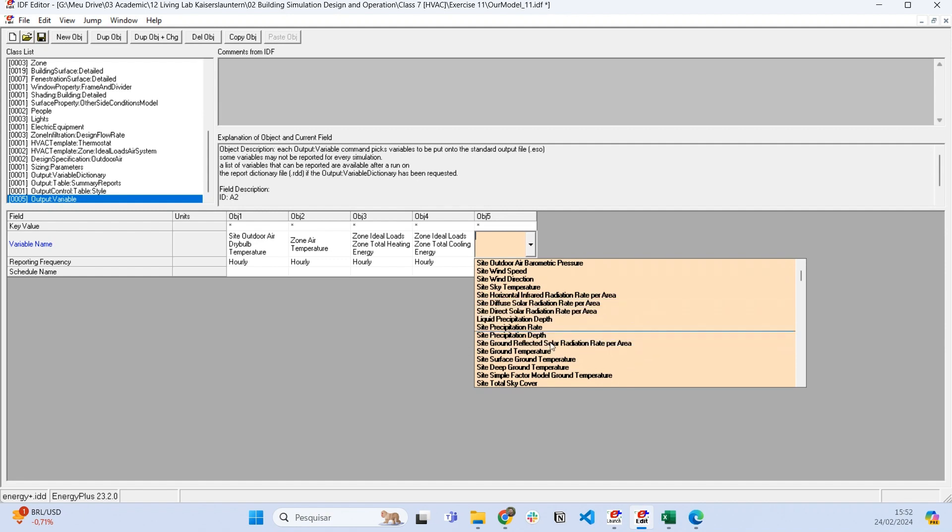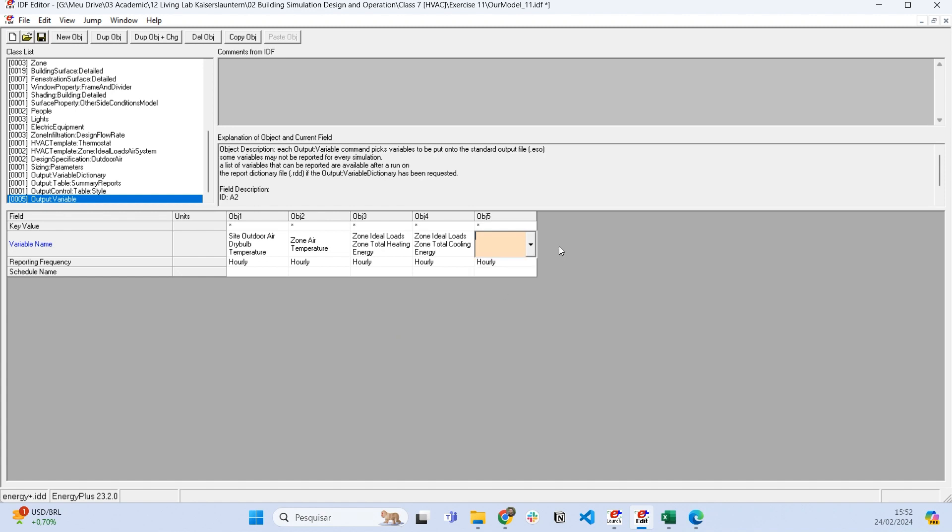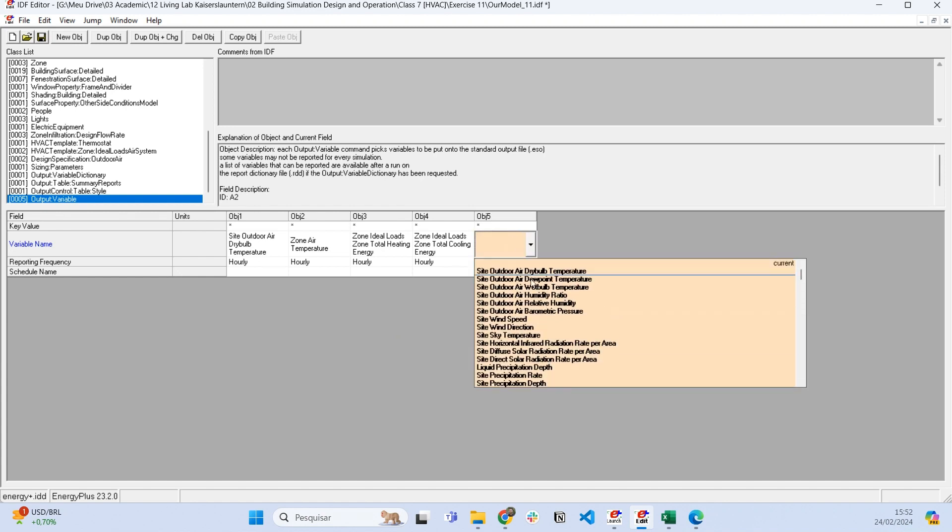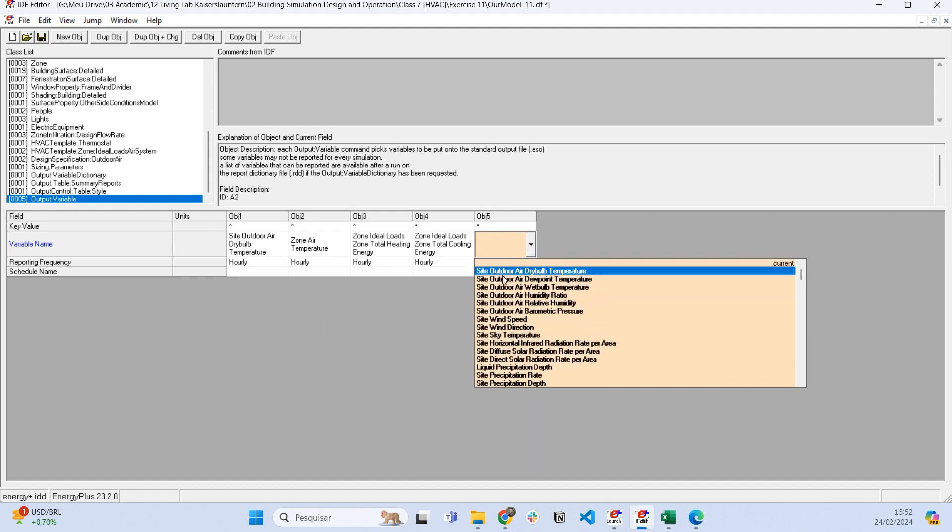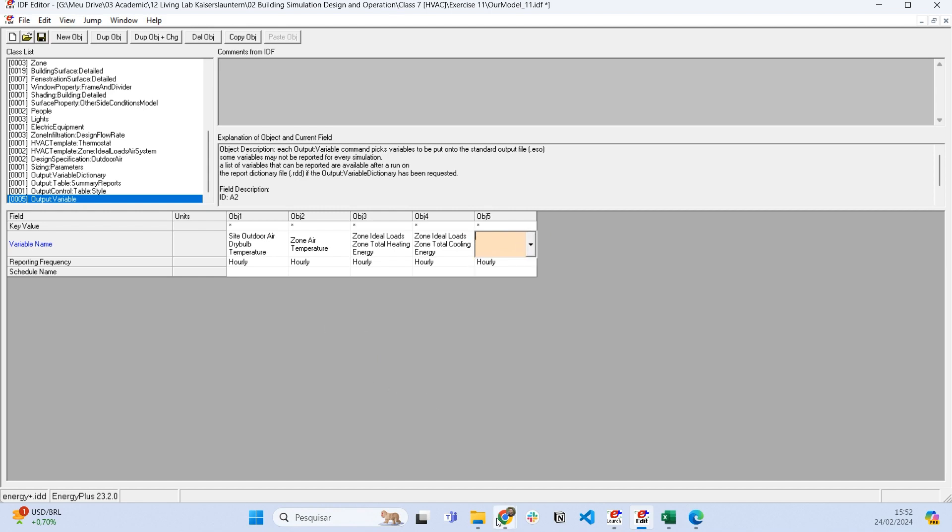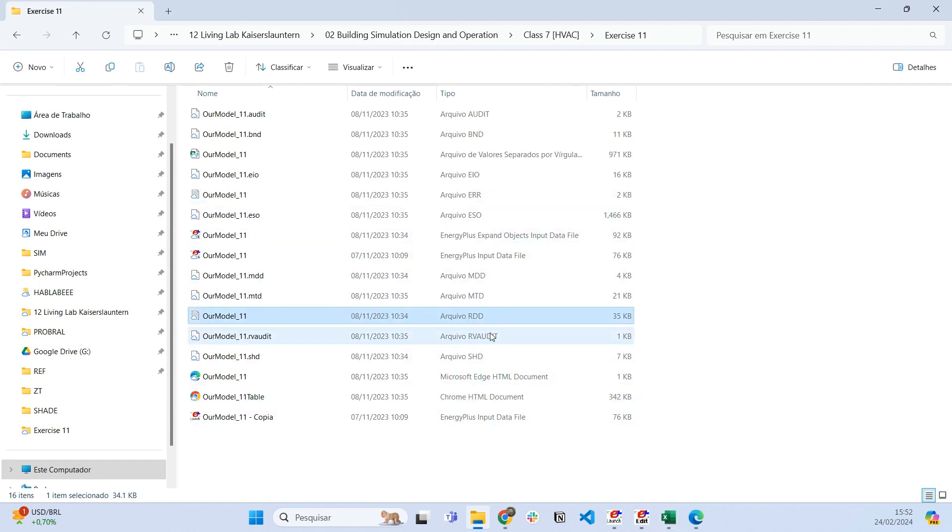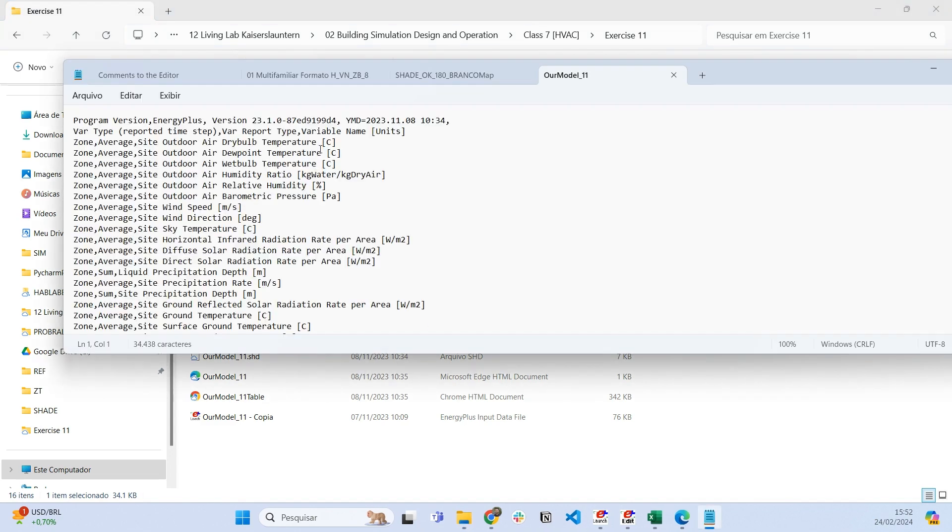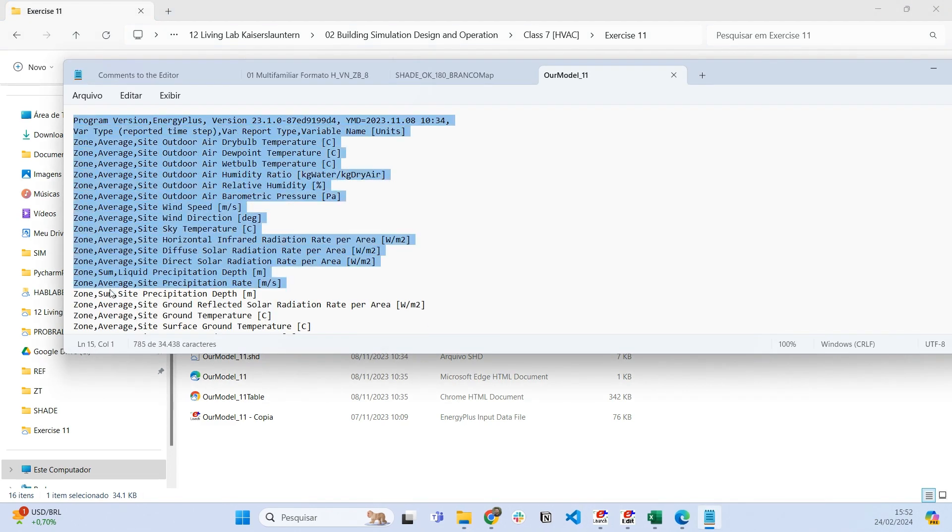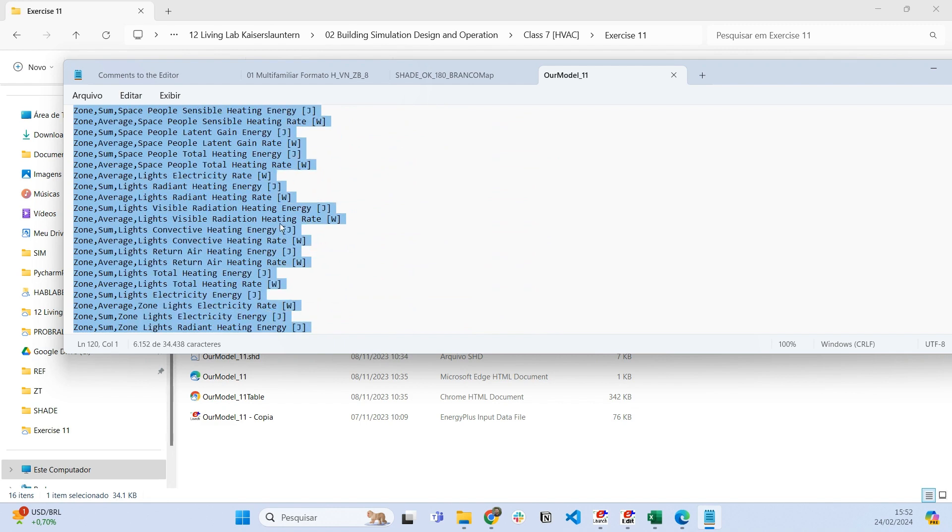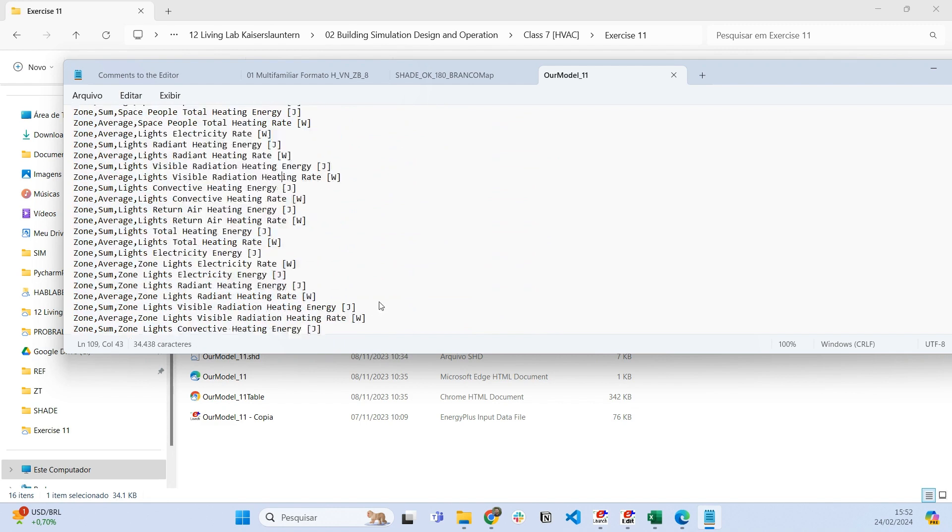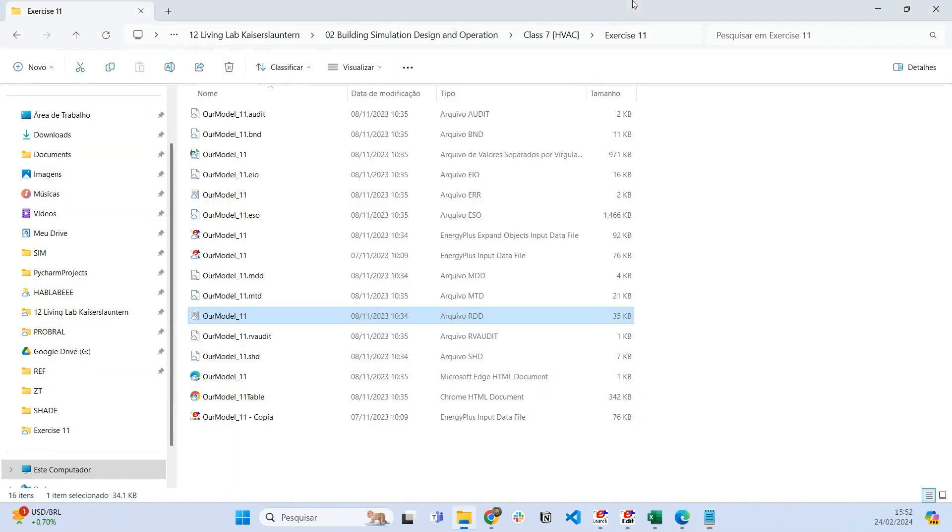It's important to mention that this list only appears after you run the first simulation. If you didn't run any simulation, there'll be no list here because this list is generated in a file called RDD. This text file contains all possible outputs from EnergyPlus. You have to run the simulation and EnergyPlus will generate this file, then the IDF will make this list available.